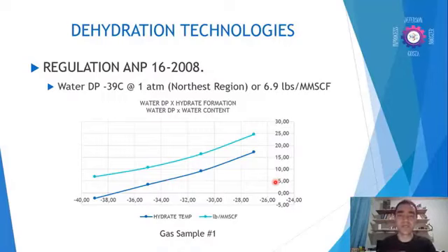by the history of my unit, by the history of my operation, I always operate above 15, or the minimum operating temperature was 15 Celsius degrees. I have 10 degrees of margin, and reducing the dew point to minus 34 should be enough in terms of operations. And that is very important because, of course, the more water content you must remove from your gas, the more expensive the technology that we use will be.